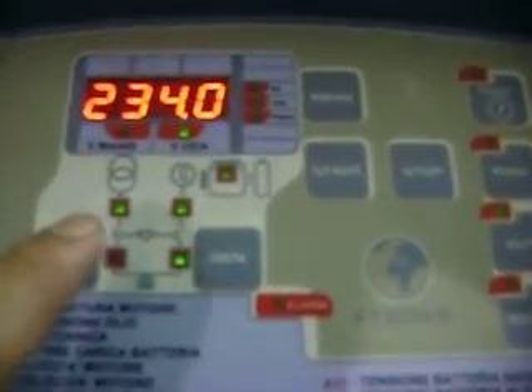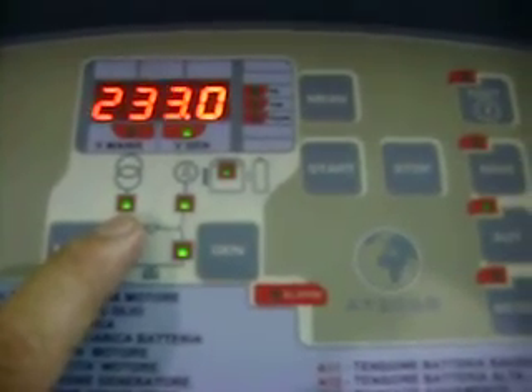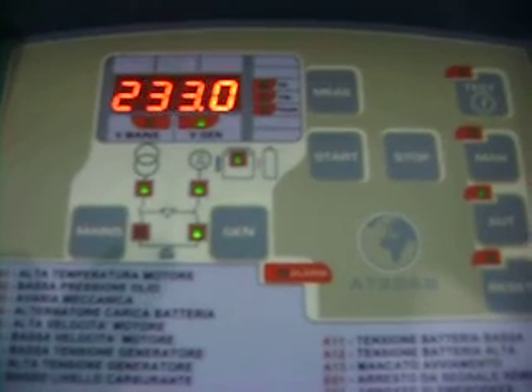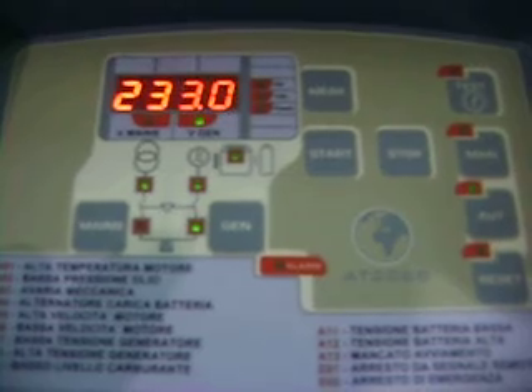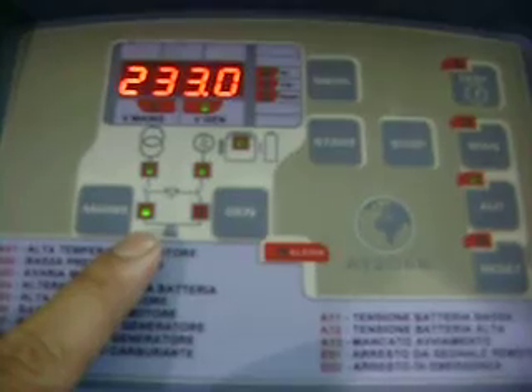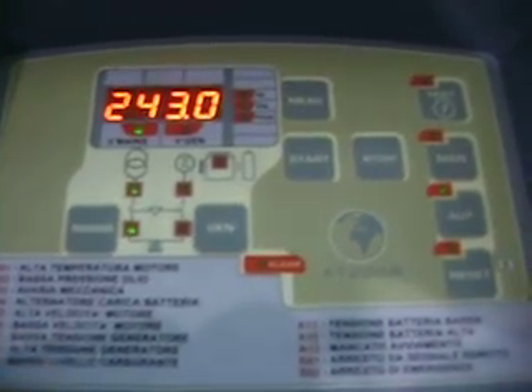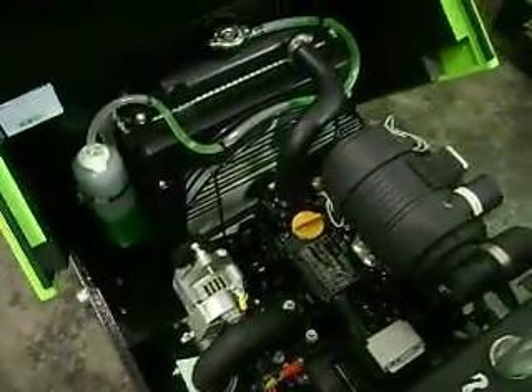You can see the mains voltage has returned. The engine is running but will switch off soon. The breaker has now changed over to the mains. The engine goes into cool-down mode and then stops.